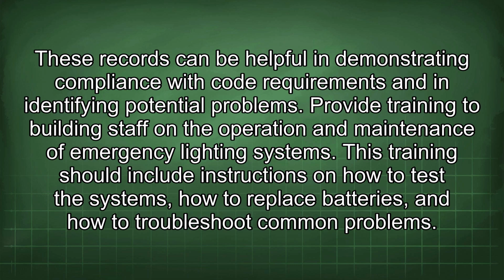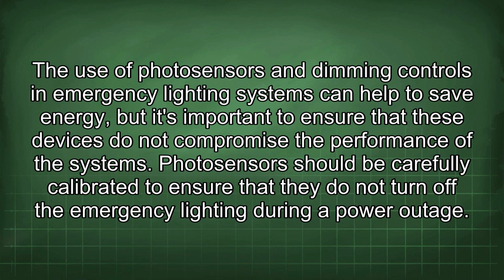Provide training to building staff on the operation and maintenance of emergency lighting systems. This training should include instructions on how to test the systems, how to replace batteries, and how to troubleshoot common problems. The use of photosensors and dimming controls in emergency lighting systems can help to save energy, but it's important to ensure that these devices do not compromise the performance of the systems.